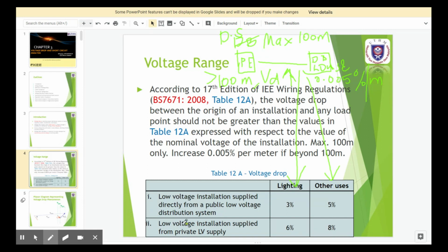And then the second one is low voltage installation supplied from a private LV supply. So for any private LV supply, the SSU or so on, you have to consider a higher percentage for the voltage drop. You can consider 6% for lighting and 8% for other uses.